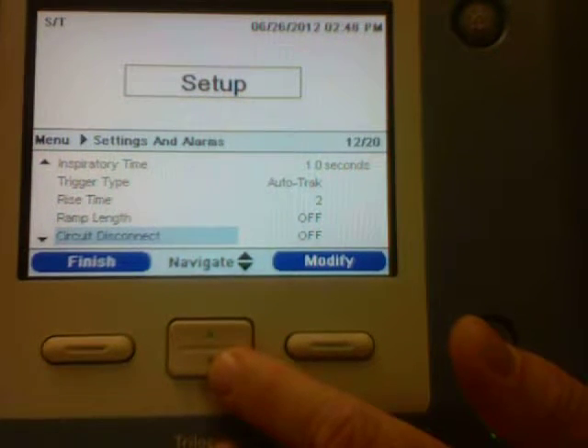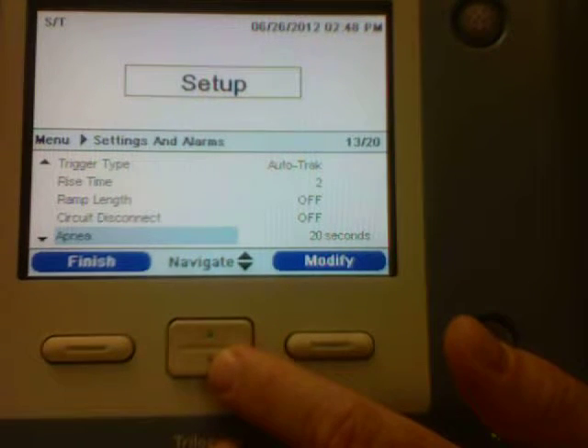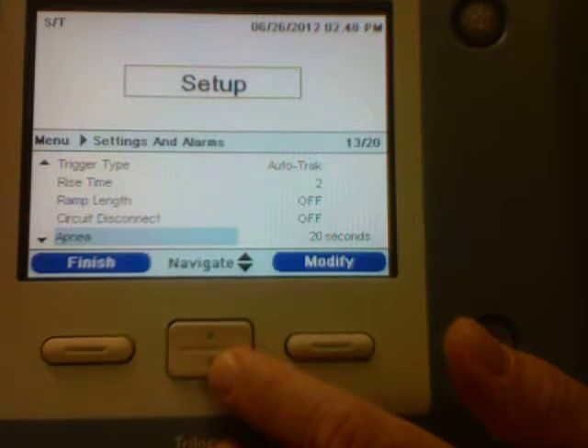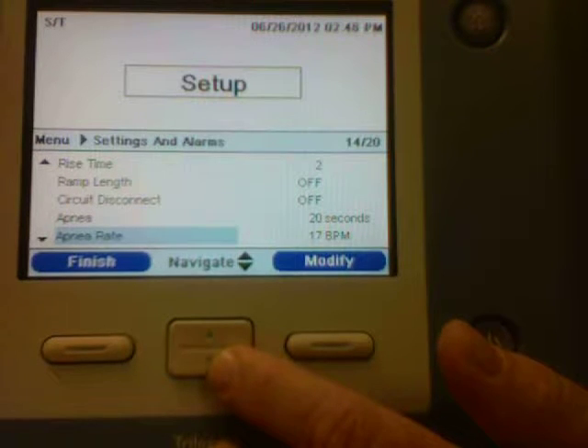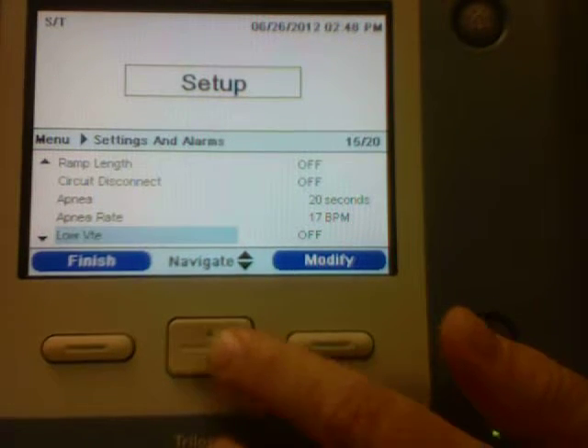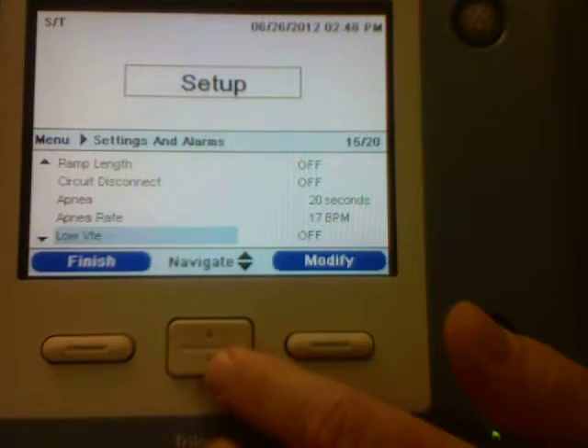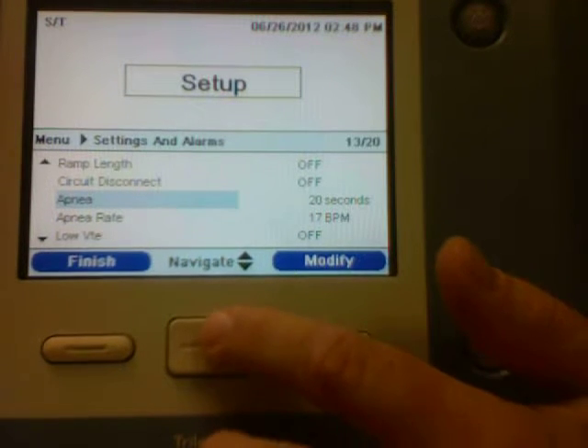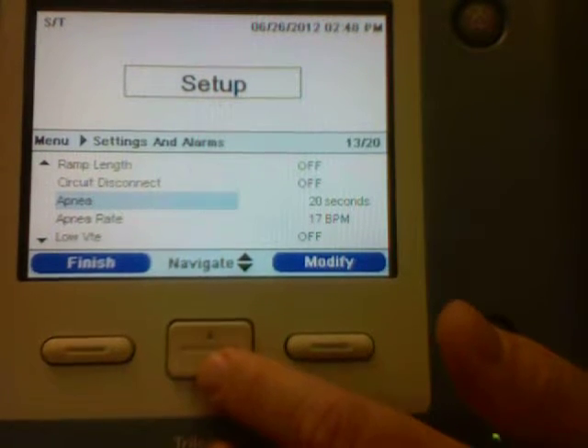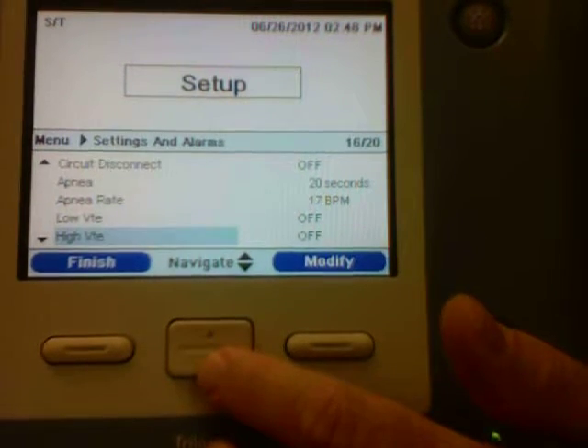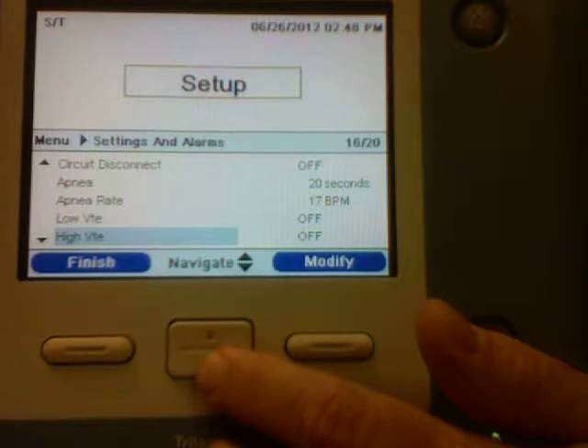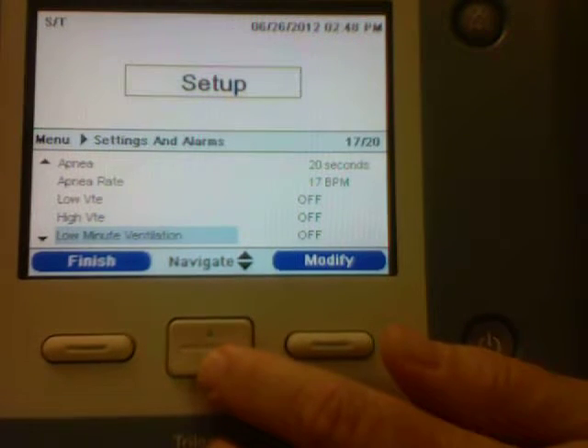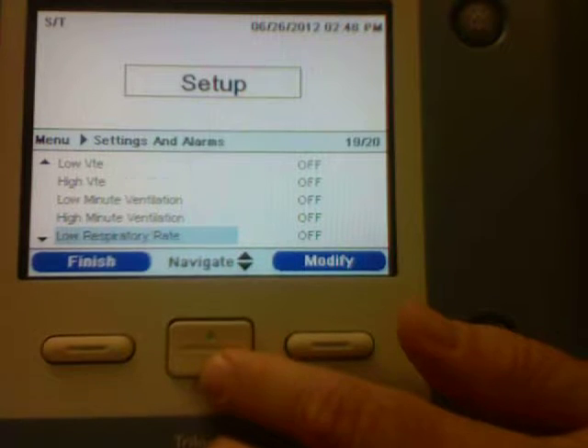So you're probably not going to use that at all. Circuit disconnect is in seconds. You can set that as an alarm. You can also set your apnea setting as an alarm, your apnea rate, if it is to go active. In the hospital, we probably are going to set these things: circuit disconnect, apnea, apnea rate, low tidal volume, perhaps a high tidal volume, low minute volume, and so on.